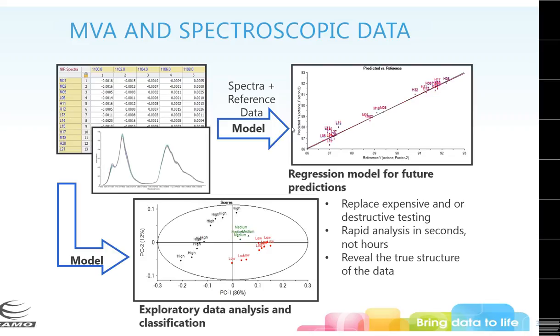With multivariate data analysis on spectroscopic data, you can use it for exploratory data analysis and classification — for example, identifying different types of raw materials or media. It also allows you to combine spectroscopic data with laboratory reference data to build regression models for prediction. This lets you replace expensive or destructive testing such as HPLC, which looks at degradants or active drug ingredient content in tablets. Because Raman is so fast, you get your analysis in seconds rather than hours or weeks, saving time and money.